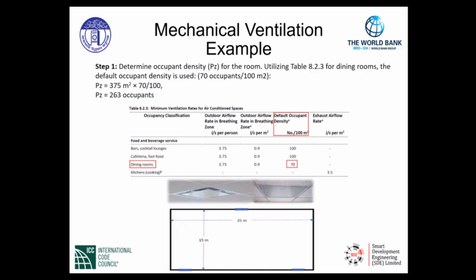Step 1 of our example, we will determine the occupant density, P sub Z, for the dining room. Utilizing table 8.2.3 for dining rooms, the default occupant density is used at a ratio of 70 occupants per 100 square meters. Viewing the table below, as you can see, the category here of occupant classification is food and beverage service. The space that we will be utilizing for our calculation is dining rooms. And moving over to the fourth column, the value 70 is our default occupant density, 70 occupants per 100 square meters. So we will pick that first.